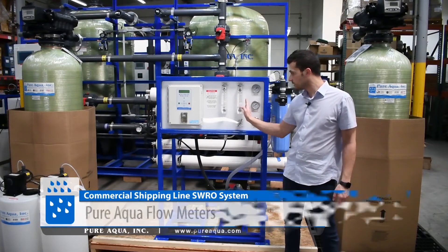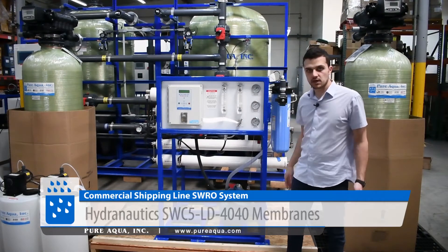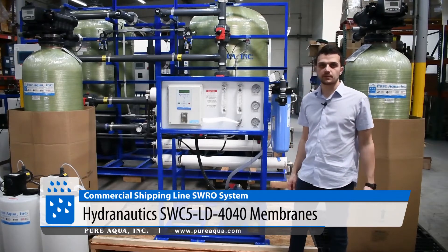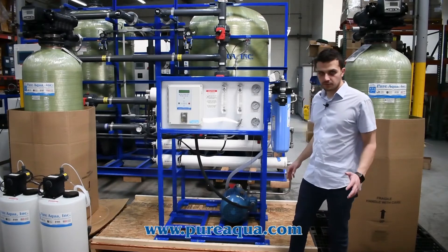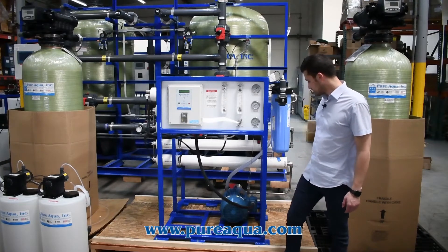We also have reject and permeate flow meters. For the membranes, we're utilizing Hydranautics SWC5-LD-4040, which are excellent membranes for these smaller-scale applications where you're feeding 10 to 20 GPM on the feed side.